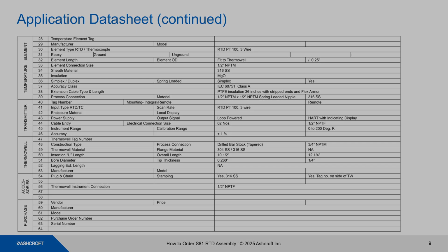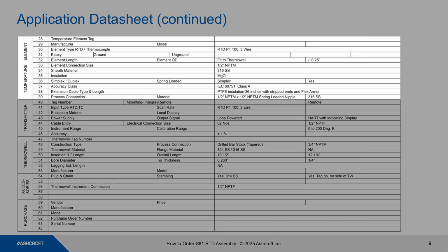Now we're going to look at the temperature element section, and we see that this is a RTD probe, 100 ohms, 3 wires. It's a 1/4 inch diameter. The length is fit to thermowell. The element connection is going to be a 1/2 inch NPT. The sheath material is going to be 316. It's going to be a single. Accuracy is going to be Class A. It's going to have an extension cable insulation of PTFE, 36 inches long with stripped ends, and it's going to have optional flex armor. The process connection is going to be a 1/2 inch NPT by 1/2 inch NPT spring-loaded nipple.